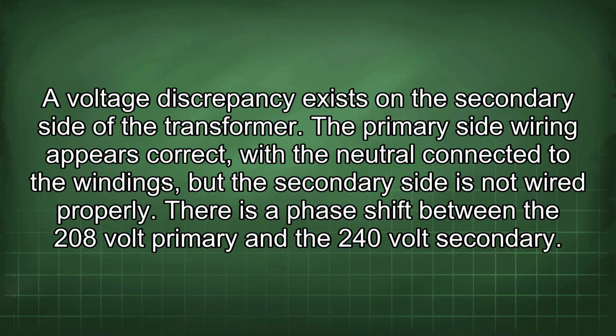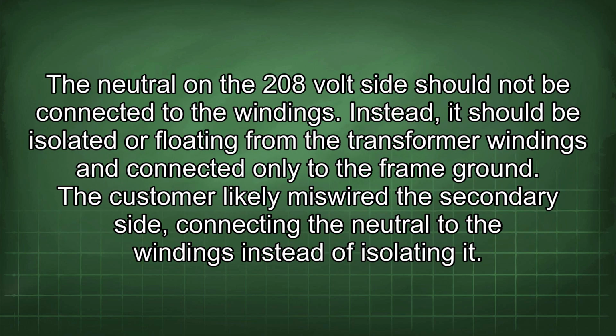A voltage discrepancy exists on the secondary side of the transformer. The primary side wiring appears correct, with the neutral connected to the windings, but the secondary side is not wired properly. There is a phase shift between the 208-volt primary and the 240-volt secondary. The neutral on the 208-volt side should not be connected to the windings. Instead, it should be isolated or floating from the transformer windings and connected only to the frame ground.